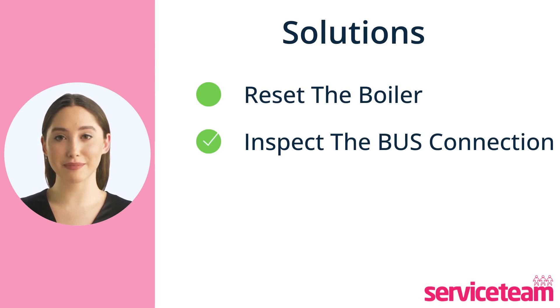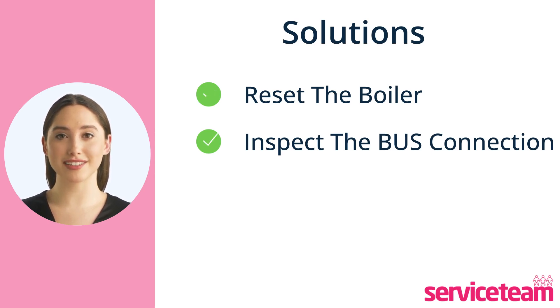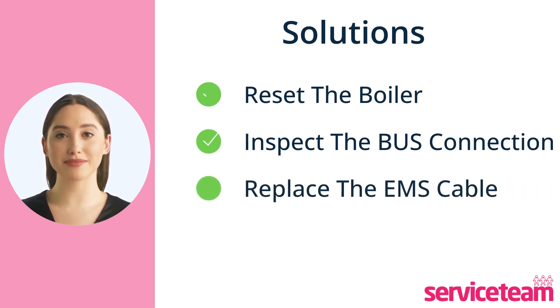Then inspect the EMS cable for any physical damage. If the cable is cut, frayed, or showing signs of wear and tear, it can lead to data transmission errors or system failure. It's best to replace the EMS cable.